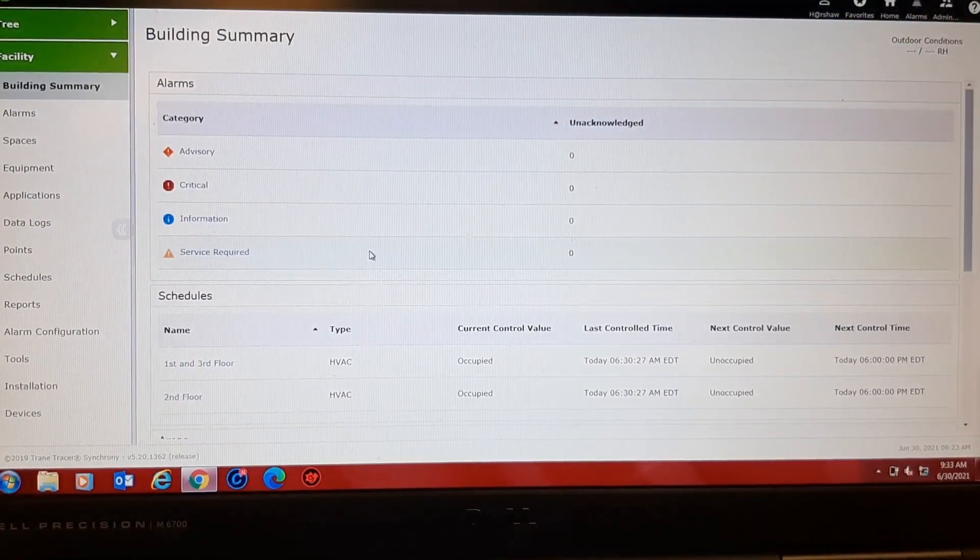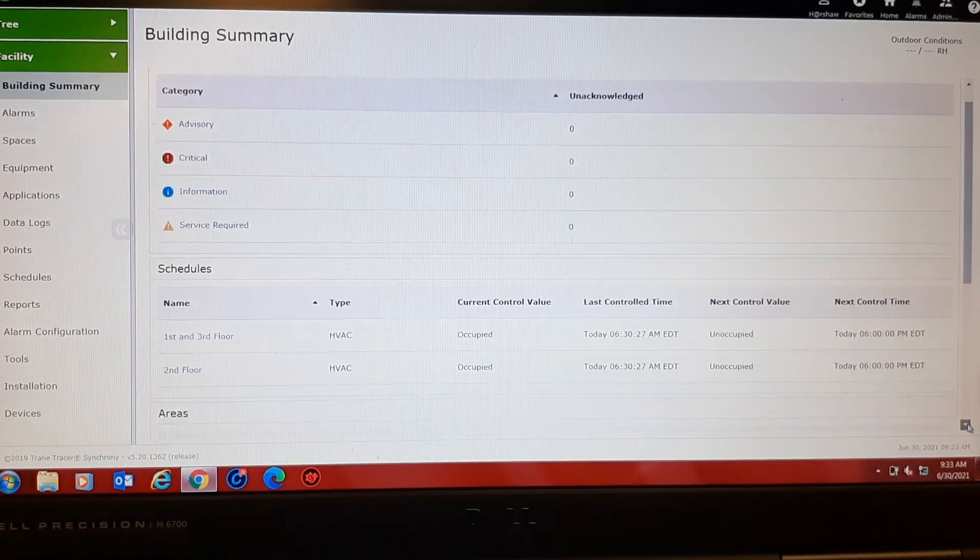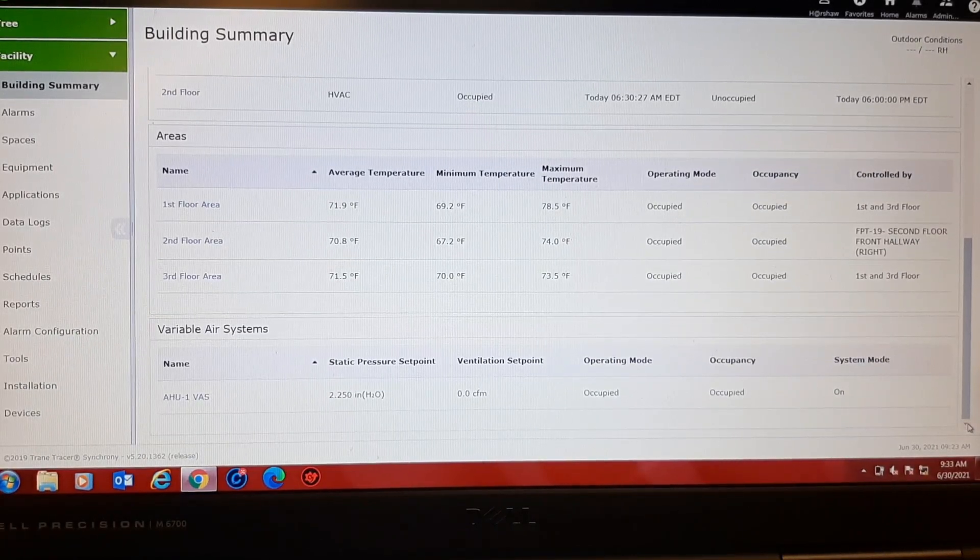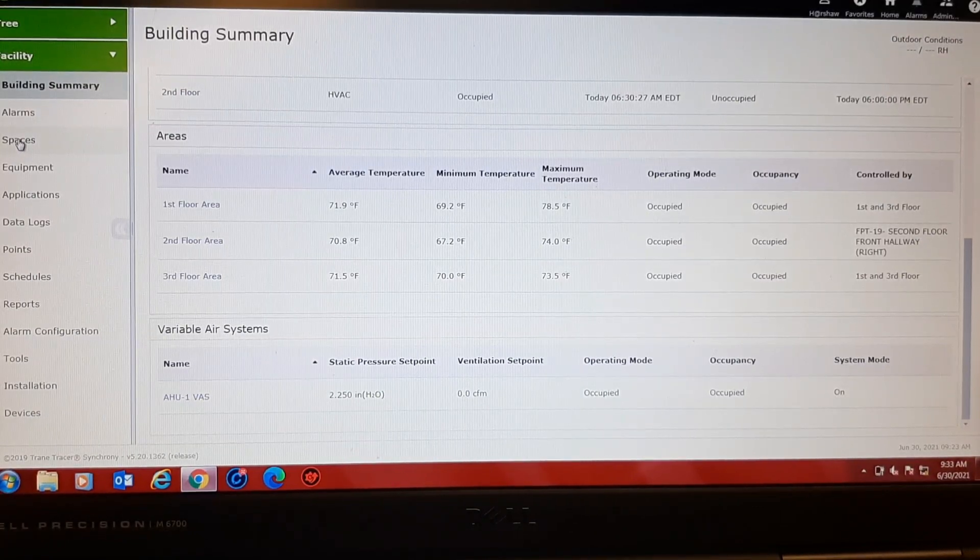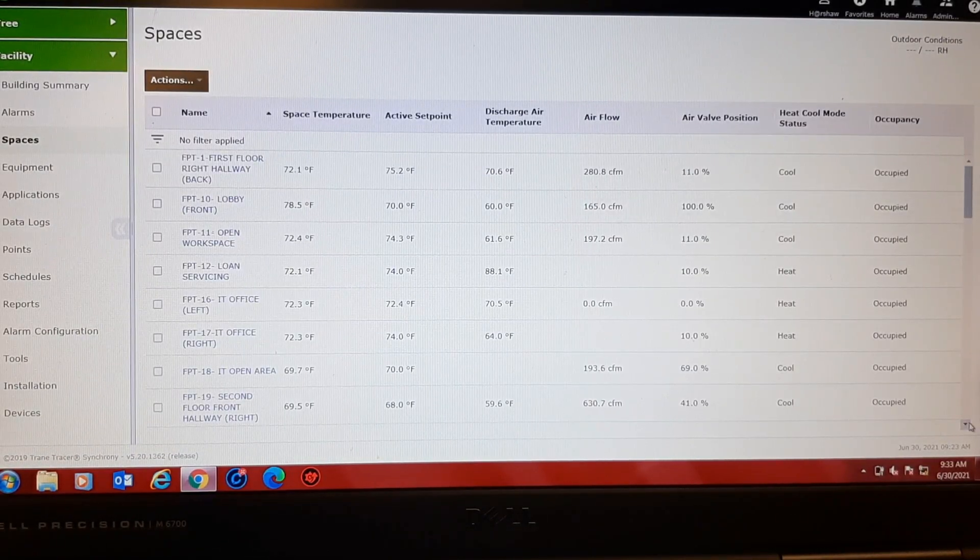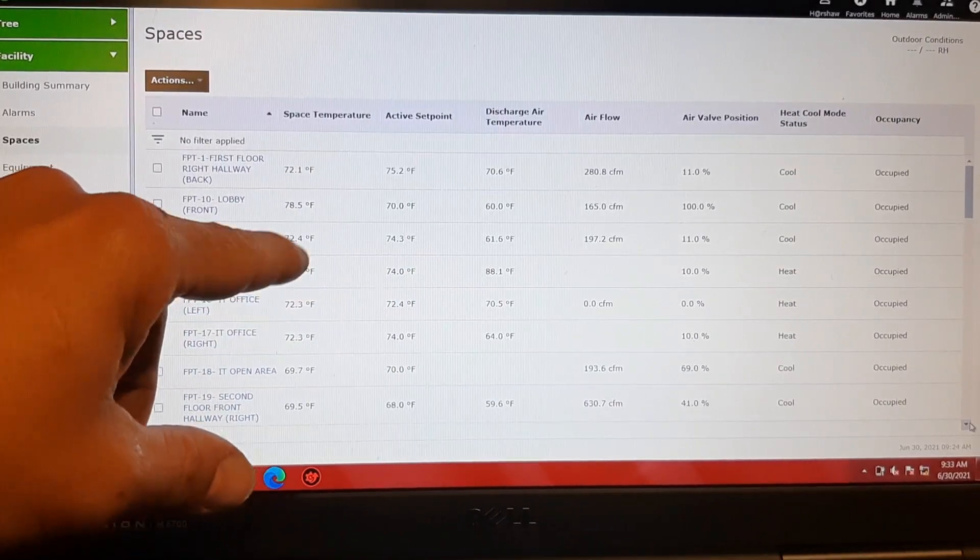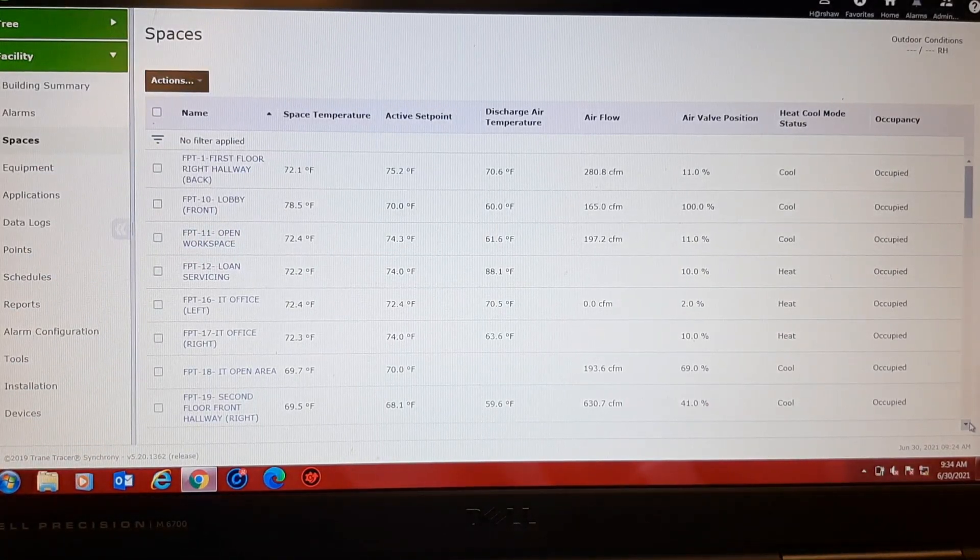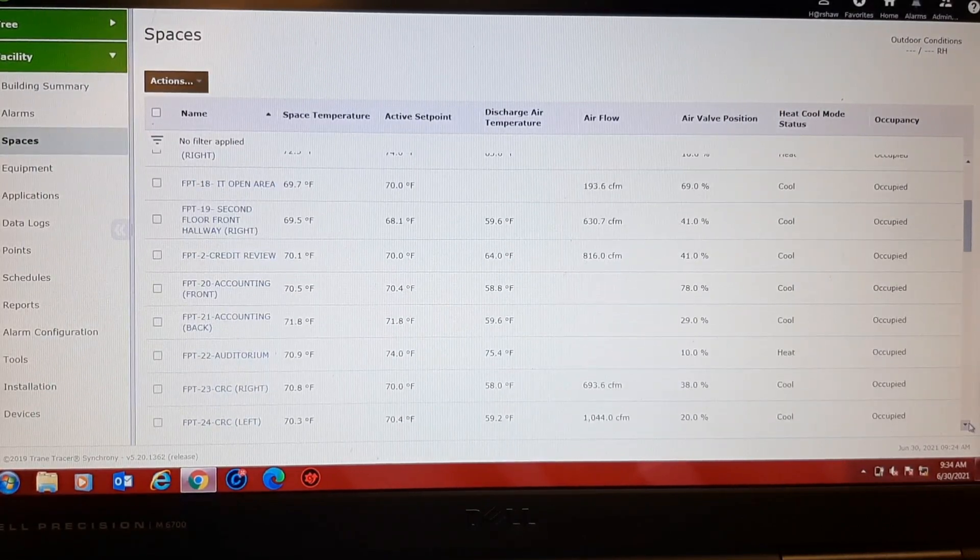So here we are. I don't see any critical alarms. Everything's occupied. Average temperatures, minimum temperatures look good. So everything looks normal there. Let's see what our spaces look like. And I'm just going to compare set point to space temperature. Front lobby is a front vestibule area, it's at 100%, so I'm not concerned about that one, it's always warm. Everything else is within a normal range or right at set point.